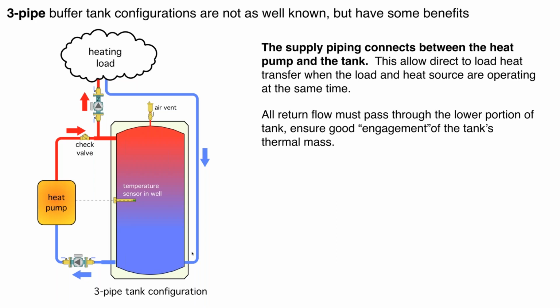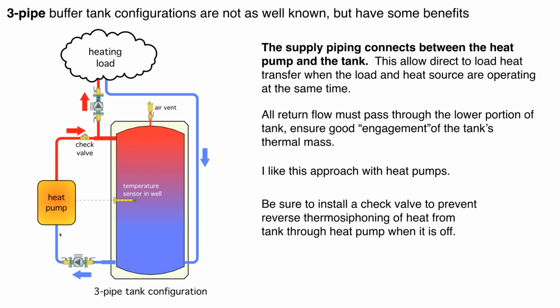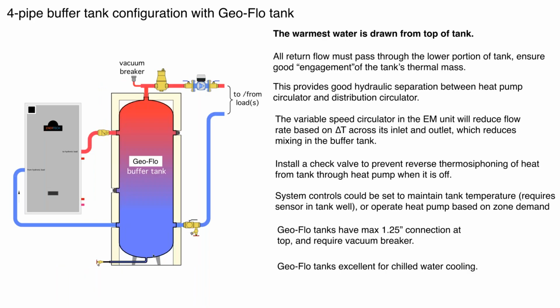I would still recommend controlling the heat pump based on the tank temperature rather than the thermostats. But I will say, with this particular option, because we always have flow coming back through the tank, that is not an absolute essential requirement as it would be with the 2-pipe. So I tend to like this approach with heat pumps, especially the direct to load transfer, and keeping this cooler water down here at the bottom going back to the heat pump, okay? And again, make sure we get that check valve in here so we don't get a reverse thermosiphon flow going backwards and dissipating heat from that tank.